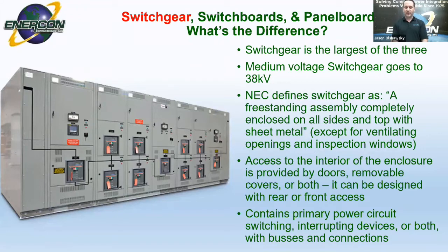The switchgear interior is accessible via doors, removable panels for front and rear access and for side access during installation and maintenance. Switchgear contains primarily power circuits for switching, interrupting devices, busing, cabling connections, and oftentimes some level of intelligent controls will be used.